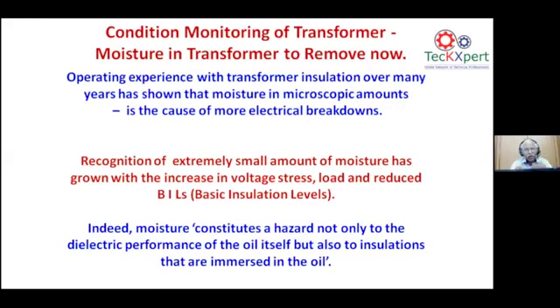This is causing a lot of electrical breakdowns. These are all the case studies which we have seen in the industries. Why has the breakdown come when all the transformer subcomponents are fine? This can be addressed by reducing the moisture which has increased in the transformer. Even small and micro amounts of this moisture definitely increase the voltage stress on the transformer, and the load as well as the basic insulation level are also put to the test.